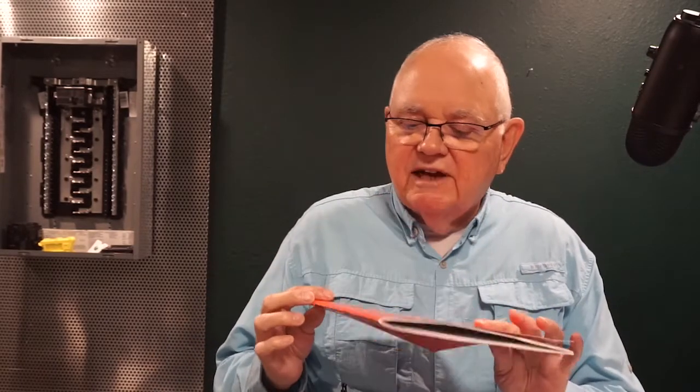Whoever's going to do that, we're going to maintain it, it says, in accordance with the manufacturer's requirements, as well as there are other sources out there like the NFPA 70B standard. The NFPA 111 standard may be another example for you, and probably you're not familiar with this standard at all. But it's the standard on stored electrical energy for emergency and standby power systems. So that may come into play for you. Certainly 70B, which is our recommended practice for electrical equipment maintenance, soon to be a standard, by the way. Okay? So, qualified persons have to install and maintain these energy storage systems.